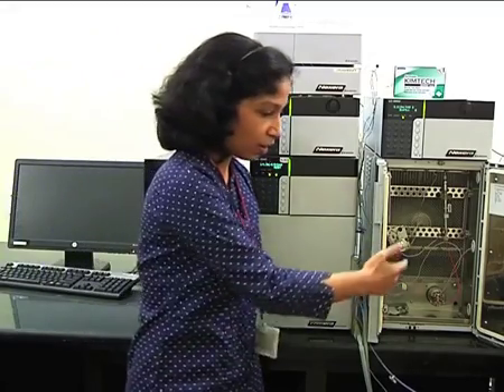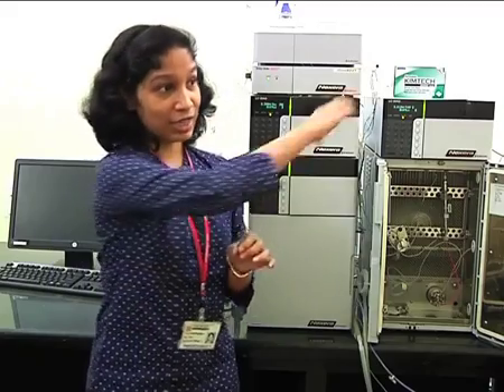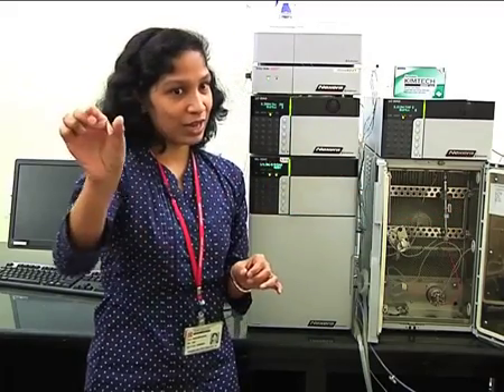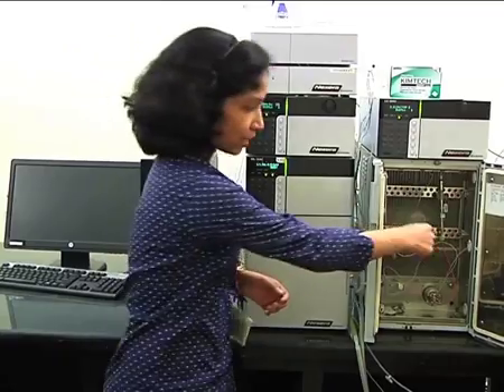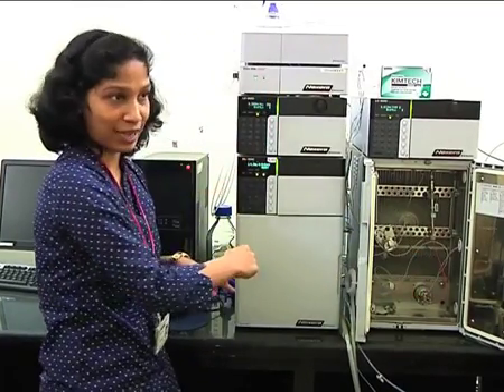There are different types of mixer available: 20 microliter, 40 microliter, 180 microliter. Depending upon your requirement, you can select which mixer is good for your analysis. Of course, the higher the volume, the better the mixing, but the system volume increases, so your peaks will come slightly late. You will have to strike a balance: whether I want to finish my analysis very fast, or I want better mixing. Depending upon that, you will select your mixer. After the mixer, your flow will go to the auto sampler.